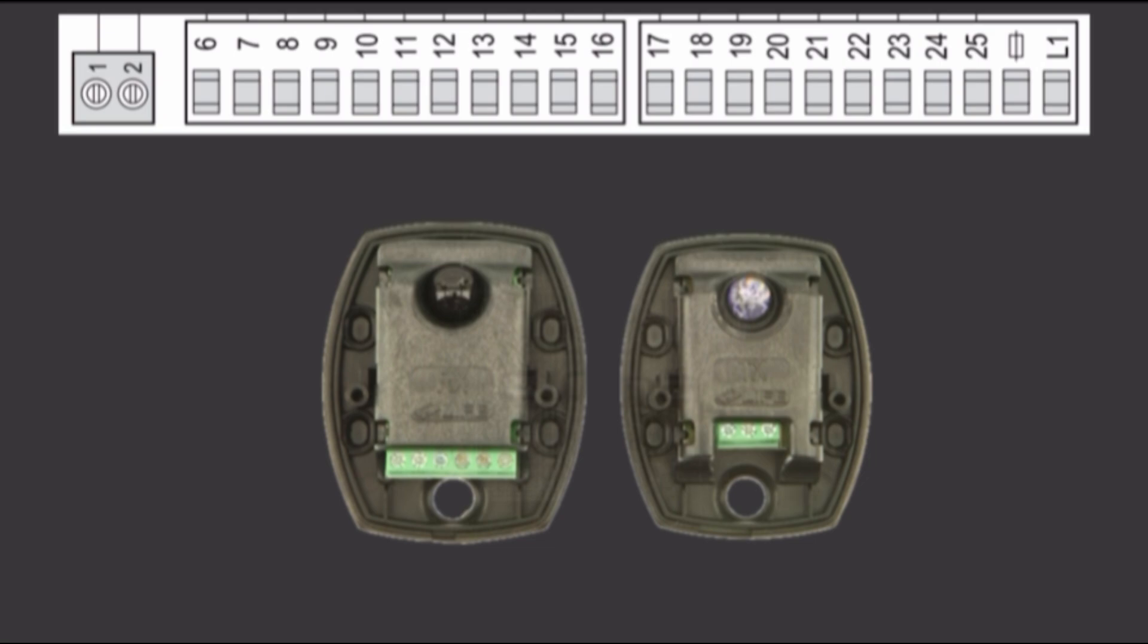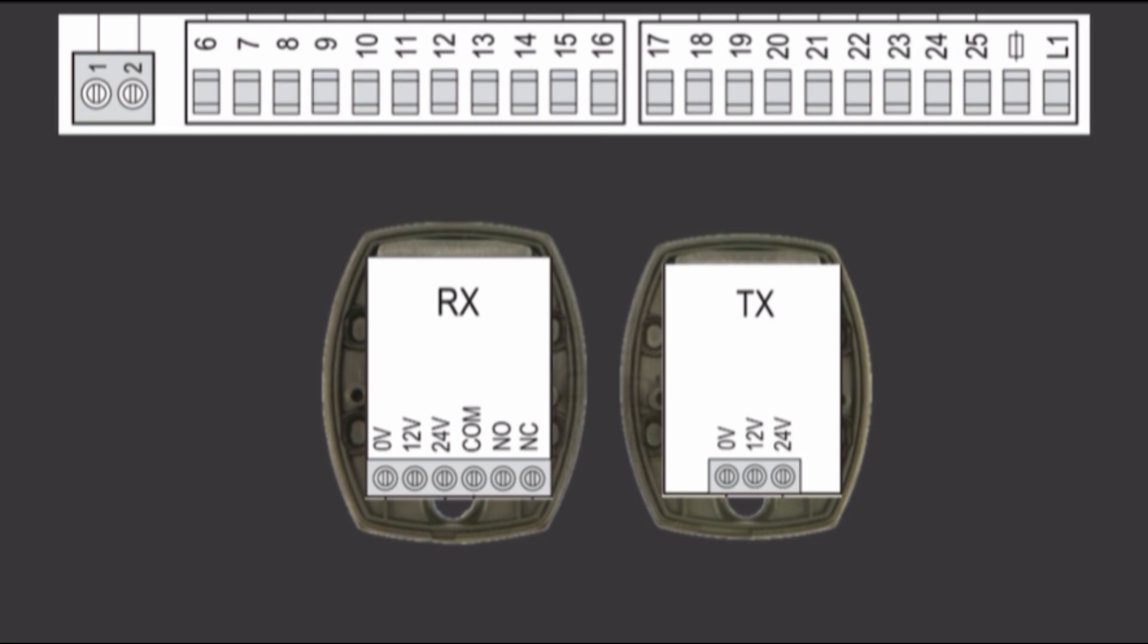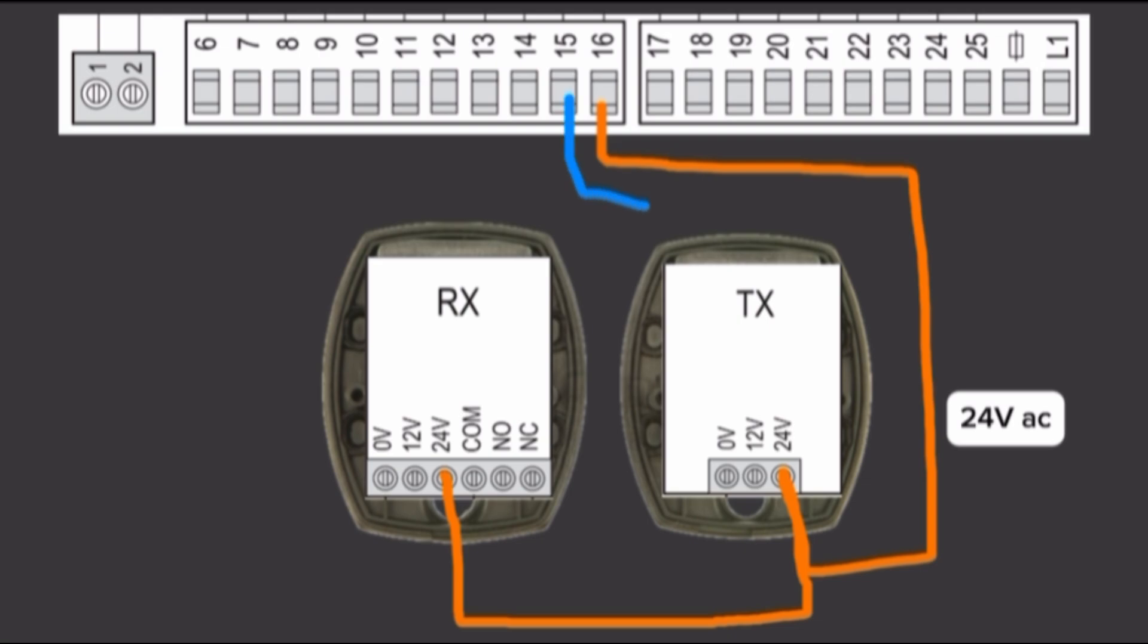This is Transmitter PhotoCell. First connect both PhotoCell power supply. Terminal 16 is 24V AC power supply. Connect this terminal to both sensors. Terminal 15 is 0V AC power supply.